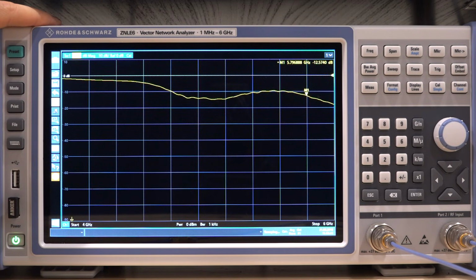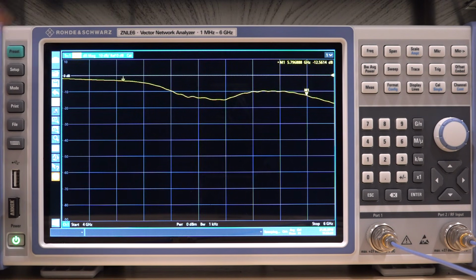But nonetheless, if this instrument has good harmonic rejection and it has good phase noise, it can operate as a 6 gigahertz synthesizer also, which would be fantastic, because then you have also a synthesizer when you have this instrument. So let's go ahead, hook it up to another spectrum analyzer and measure the performance across frequency and see if it can be used for that purpose.